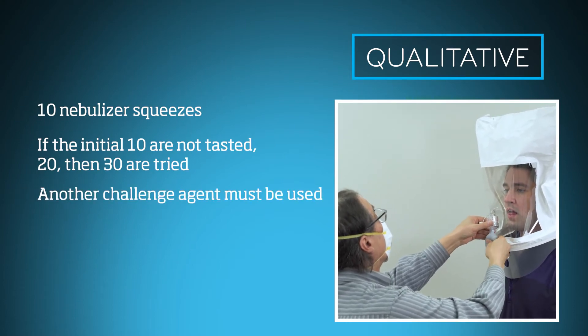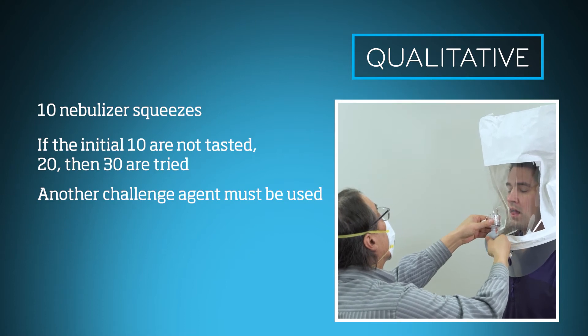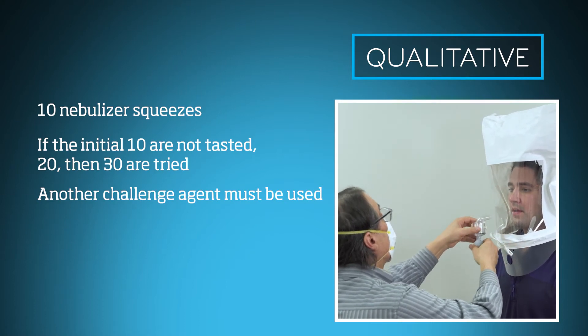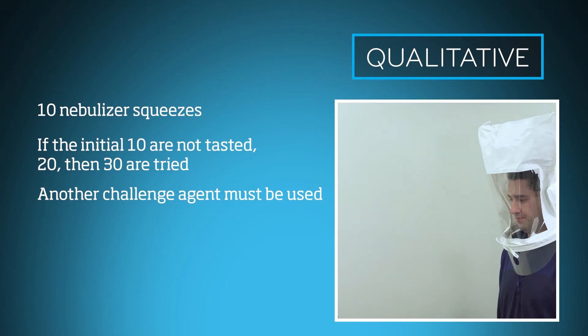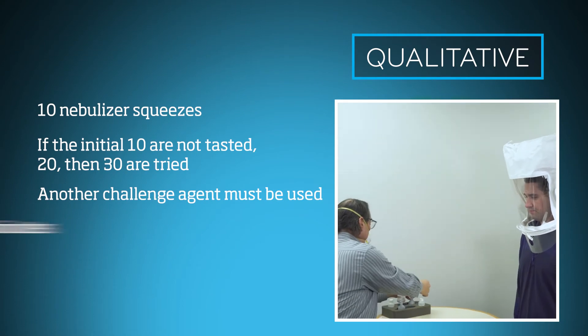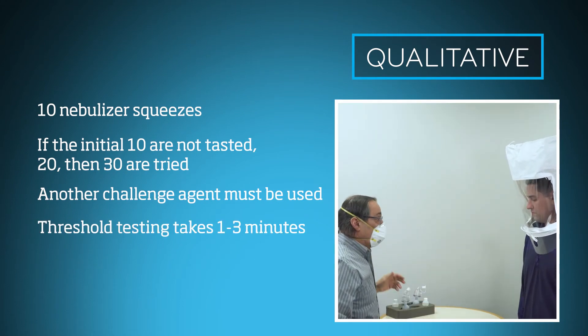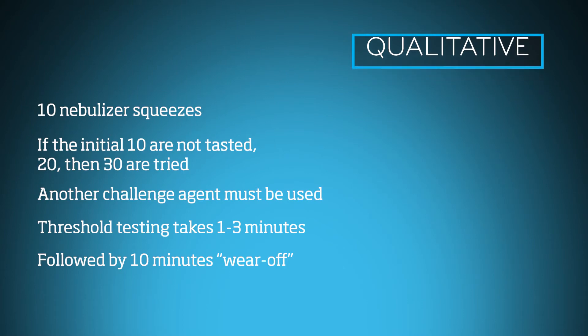If the challenge agent is not sensed after 30 squeezes, another challenge agent must be used. The threshold at which the challenge agent is detected is noted and determines the number of nebulizer squeezes used during the fit test exercises. The threshold testing takes approximately one to three minutes, followed by approximately 10 minutes or more of wear-off time before the fit test is started.